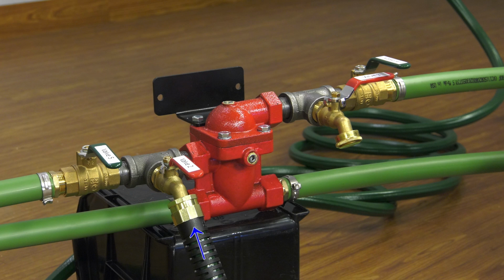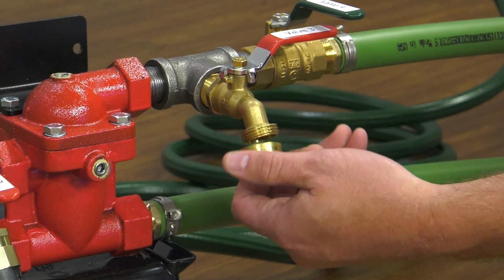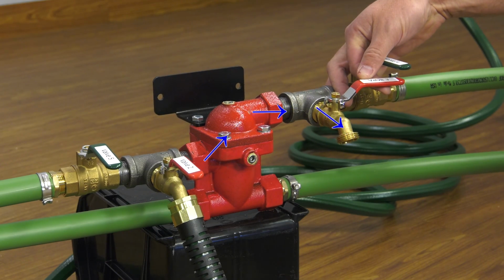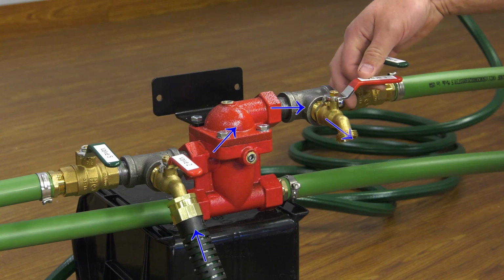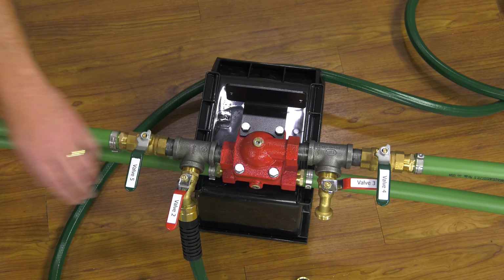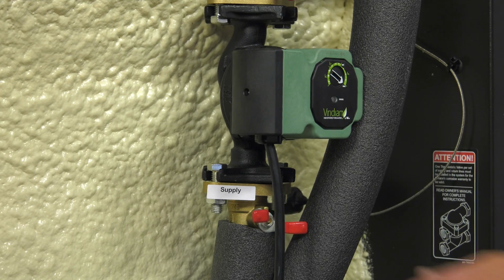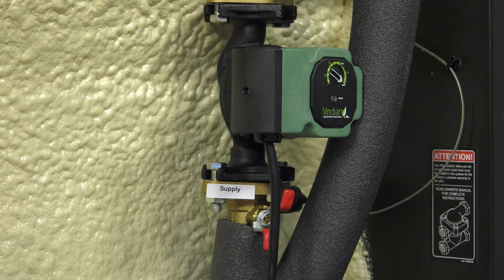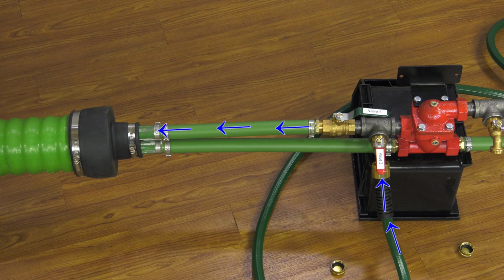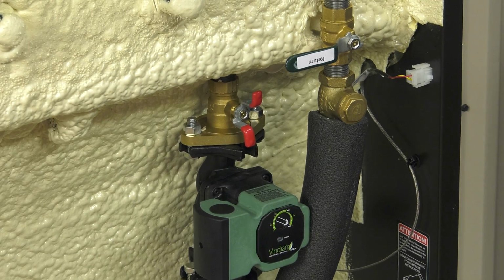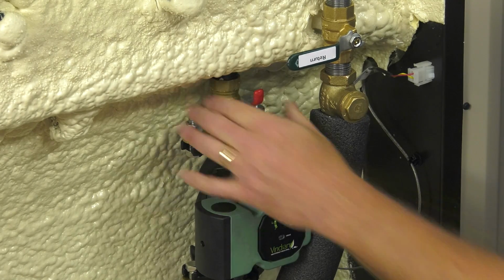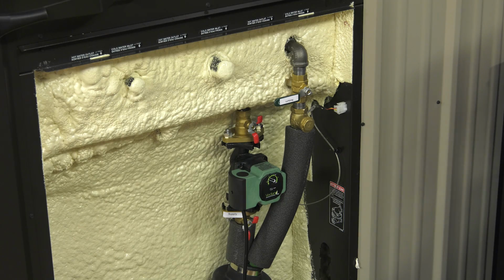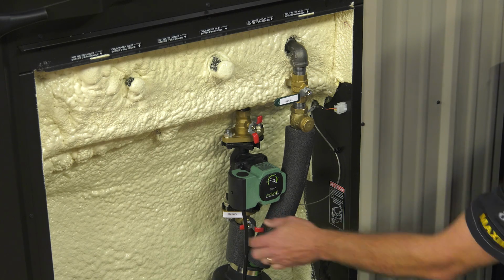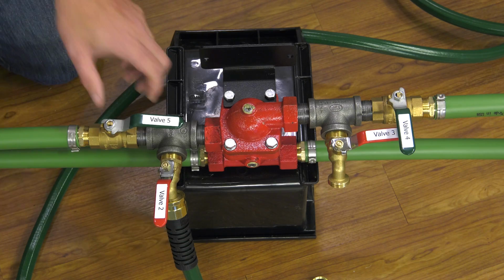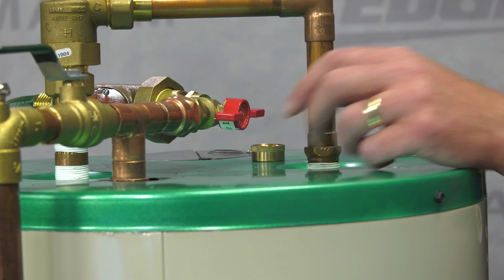This step begins filling the system with domestic water and purging the hot supply line and thermostatic valve. Remove the cap from valve 3 and open valve 3 slightly to purge the air from the thermostatic valve body. Close valve 3 when the air is purged. Next, open valve 5 and open the valve on the hot supply line of the outdoor furnace. Water will purge the air from the hot supply line. The valve and attached fittings on the outdoor furnace will become cold as water starts filling into the outdoor furnace. Do this for 5 minutes and then close the valve on the hot supply line of the outdoor furnace. Next, close valves 5, 2, and 1.